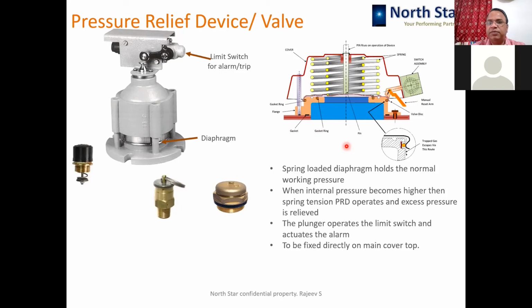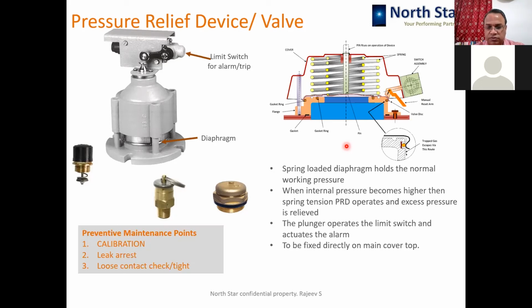So you can very easily set back the PRD and resume the operation, but please do a proper investigation into why the PRV operated. And after conducting some basic electrical tests like MBT or ratio or just insulation resistance, if you find everything right, then only you reset and resume the operation. It is true for the Buchholz relay also. When the Buchholz relay operates, we find that many times people just release the air or gas from the Buchholz relay, reset it and restart the transformer. And eventually the transformer fails because of such careless action. So operation of protective devices, especially Buchholz relay, OSR, PRD, is to be taken very seriously, and transformers are to be recharged only when you have made doubly sure that everything is fine inside the transformer, because these devices will not operate just like that for no reason. Okay, so that is to be taken care of.